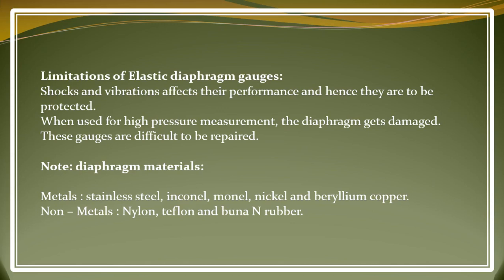When used for high pressure measurement, the diaphragm gets damaged. These gauges are difficult to be repaired. As you can understand, this is a metallic or an elastic, so when we apply a higher value of pressure, the diaphragm is ruptured, so the output is affected, and it's very costly to repair. So we normally use diaphragm type gauges for medium pressure.